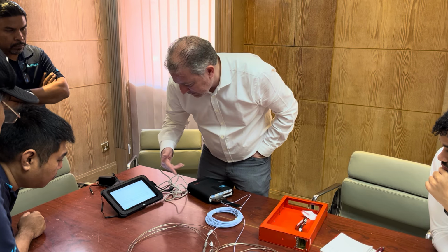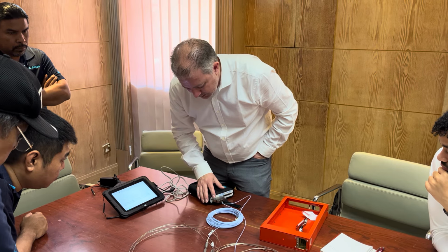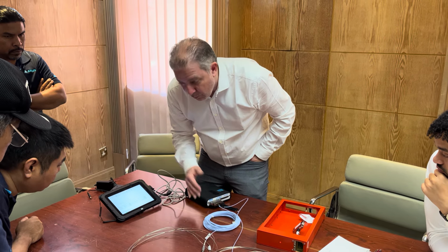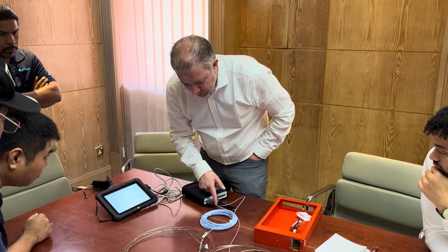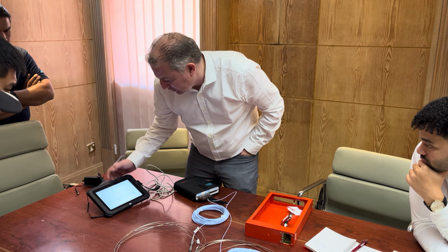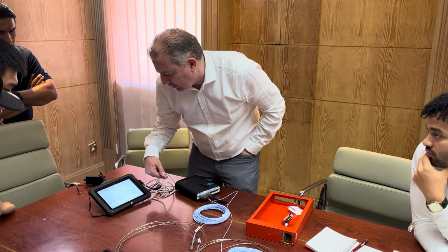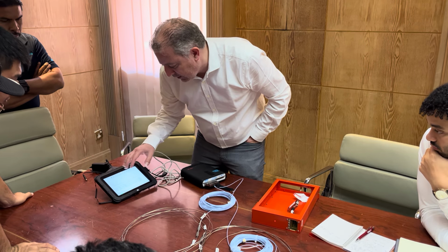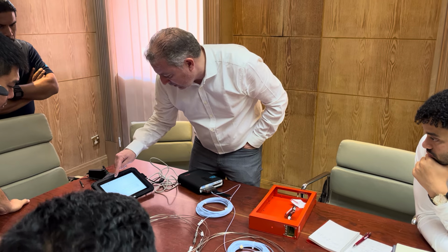And then I can see in expert mode this loop from one end or from the other, because I have access to both ends, so I can switch injection to see what's going on the other side. Okay, so now it sounds like everything is good. I can do a health check.